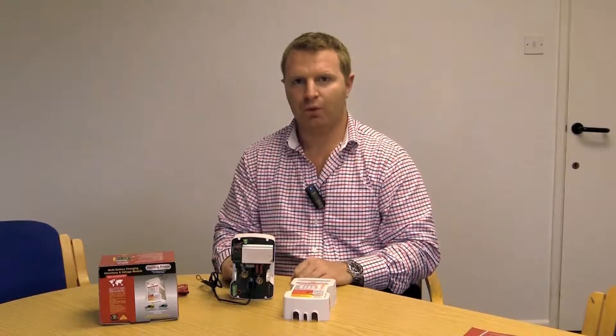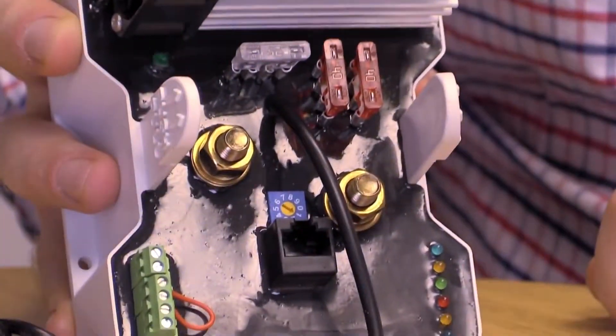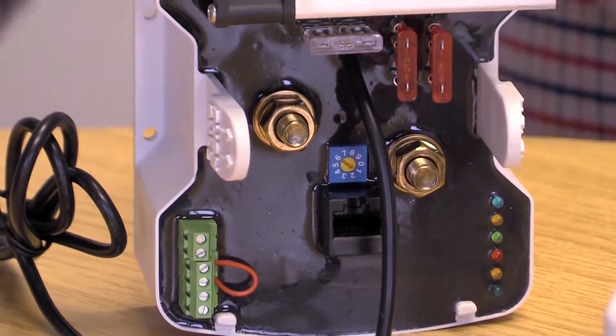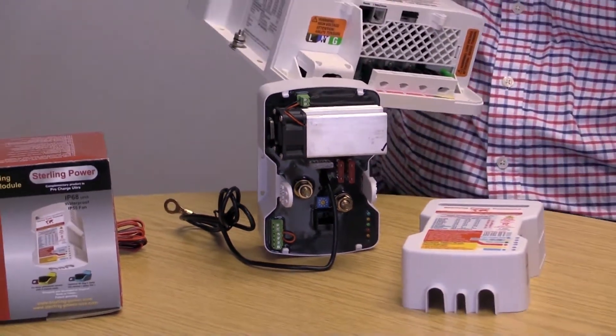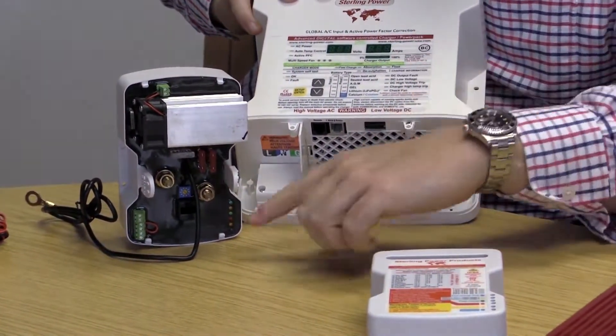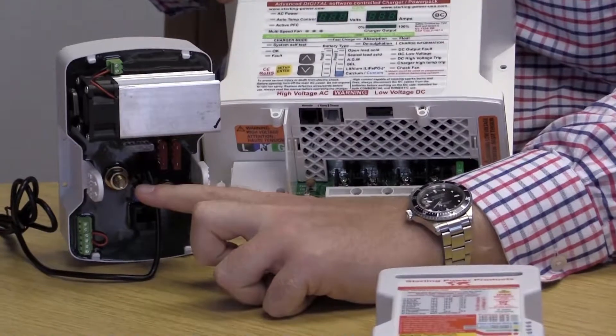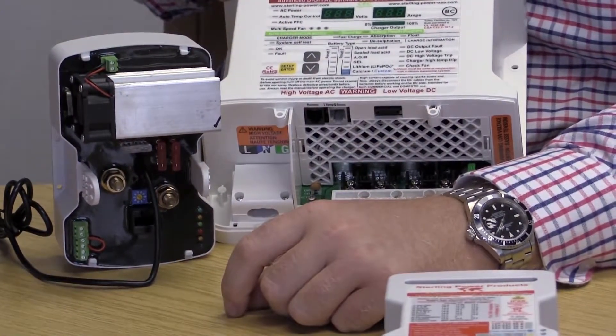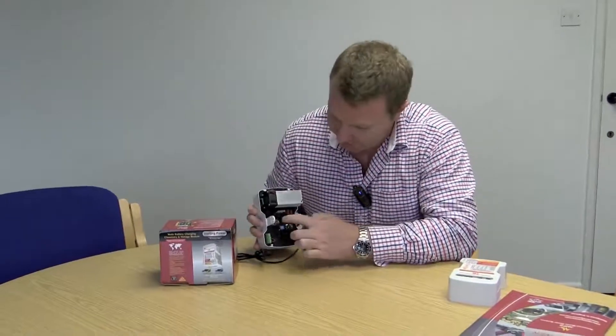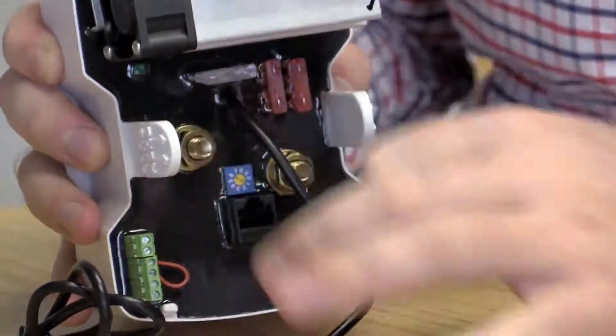This is how you wire up a battery chemistry module. You have two terminals — one is the input, connected to your battery charger, and one is the output, going to your 12 or 24 volt battery bank depending on the model. One positive output from the charger goes to the BCM input terminal; the BCM output terminal then goes to your battery bank. After installing the positive input and output cables, wire up the negative, and everything is fully installed. Make sure everything is fastened down well.